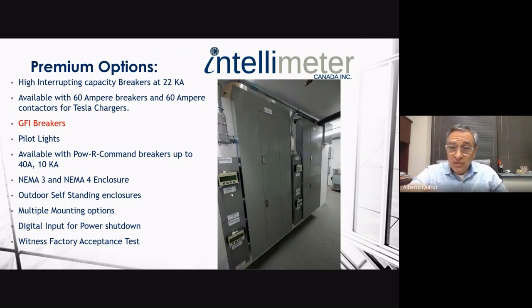One thing important for you to know is that Intellimeter is the only company - you can ask sales if this is true - but we're the only company that can offer you a witness factory acceptance test, where we put your purchased equipment on a load bank and simulate the loads of all those chargers. We give you remote access with a video camera so you can see what the system is doing, and a terminal so you can see online how the EVCMC is curtailing and managing these loads based on the conditions it will face in the field.